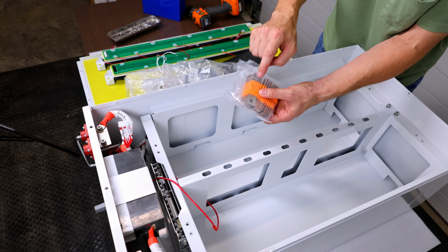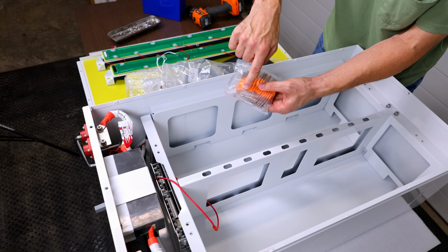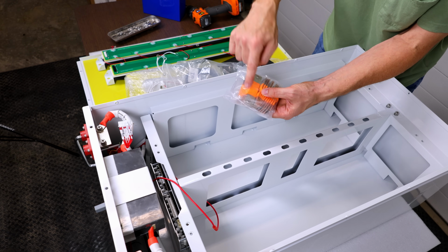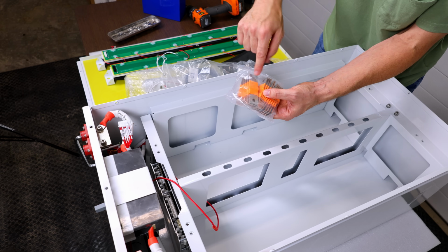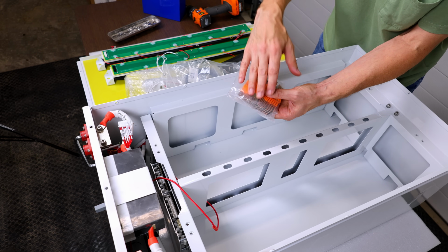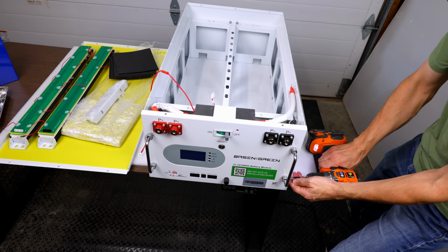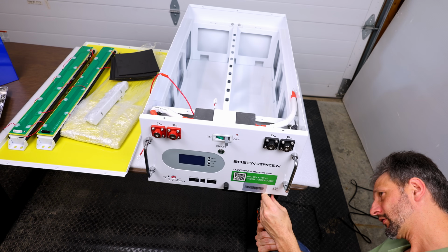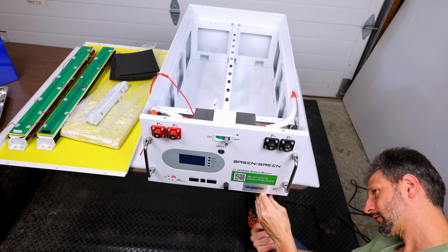And I really like the flexible bus bars. Now, these don't have an additional mount for the sensing wires, so you have to put it in with the terminal. An additional mount is nice, but as long as you torque everything down, it should be okay. Working on this table makes it a lot easier to get the screws from the underside.